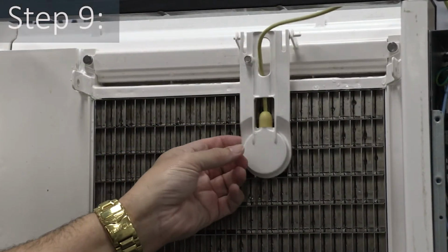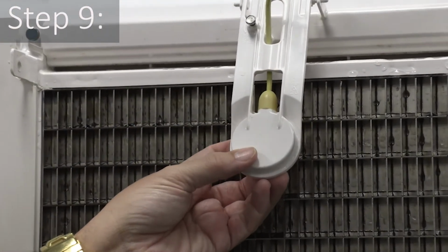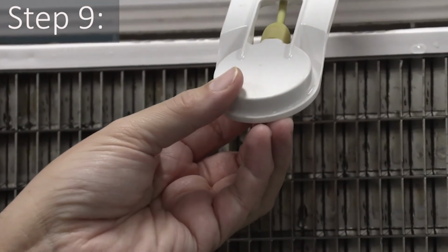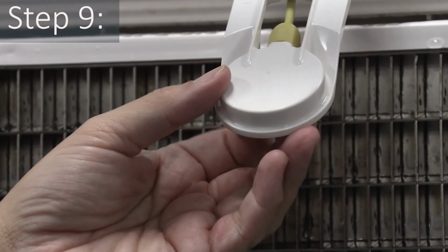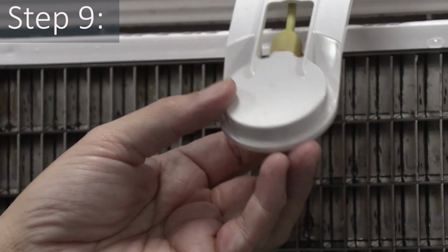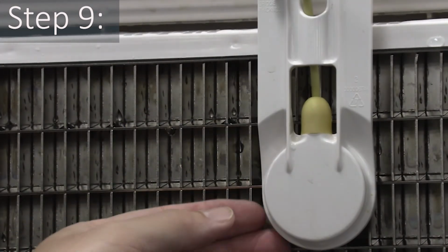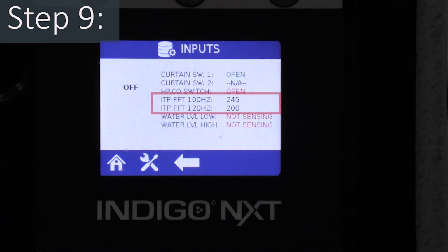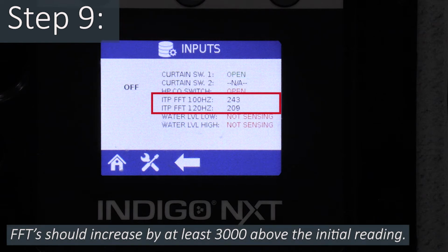Step 9. Remove the water curtain or splash shield if present. Lift the ITP and carefully tap on the face of the probe with your finger for at least 10 seconds. The ice probe FFTs should increase by at least 3,000 above the initial reading.